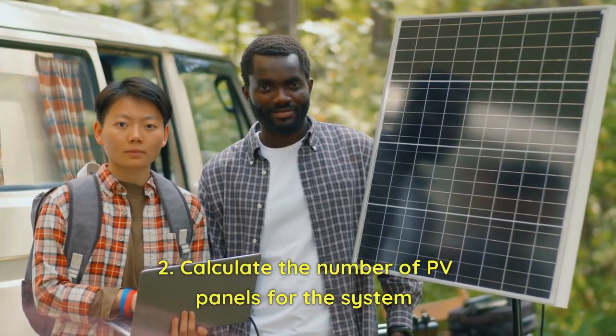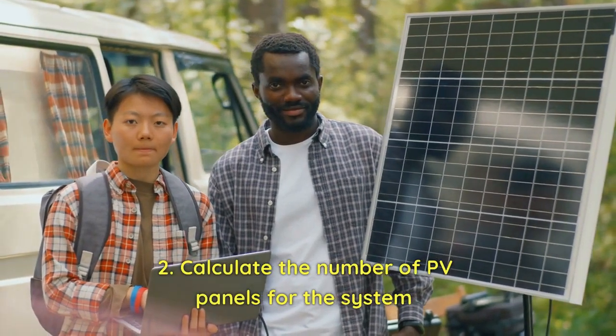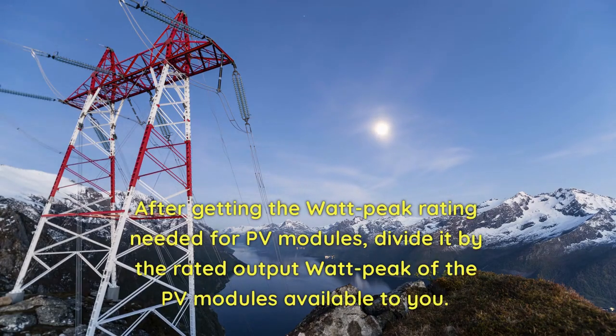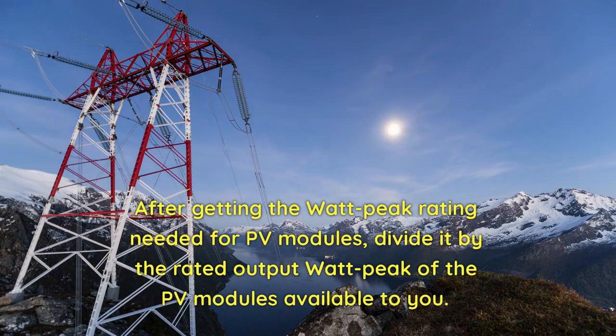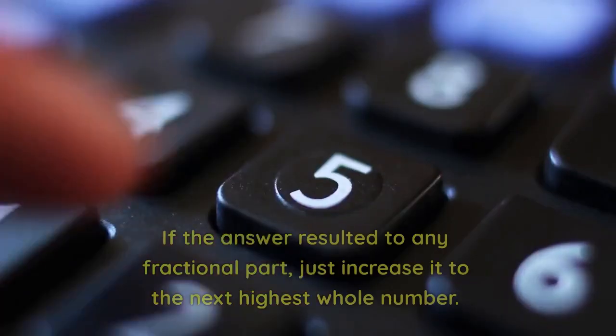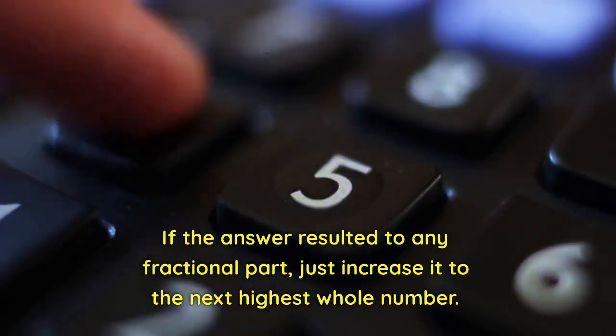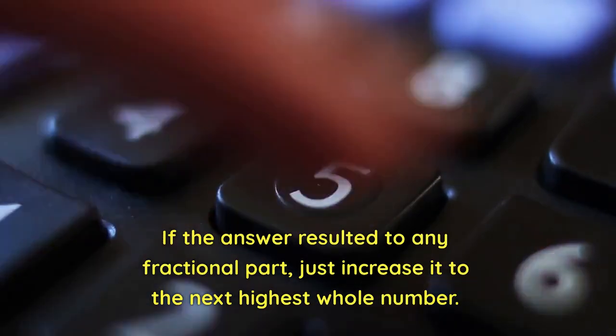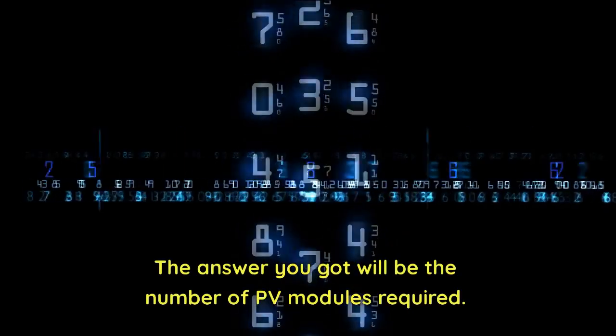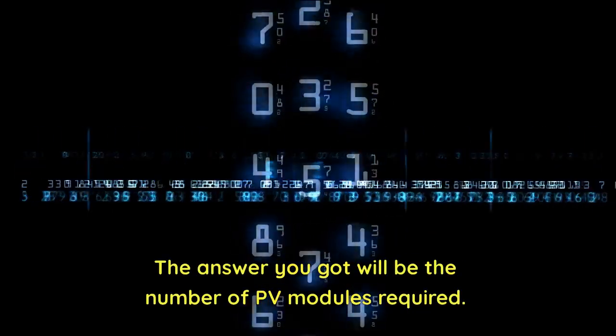2. Calculate the number of PV panels for the system. After getting the watt peak rating needed for PV modules, divide it by the rated output watt peak of the PV modules available to you. If the answer resulted in any fractional part, just increase it to the next highest whole number. The answer you got will be the number of PV modules required.